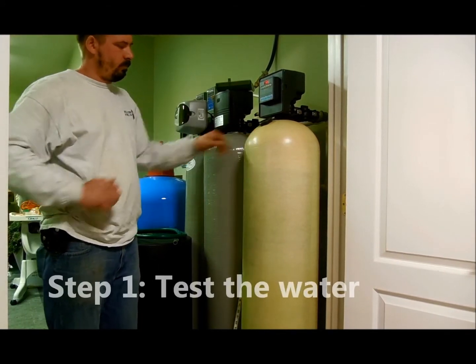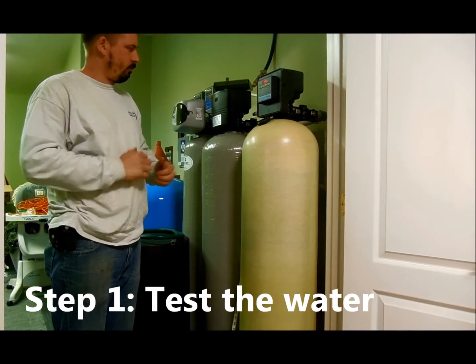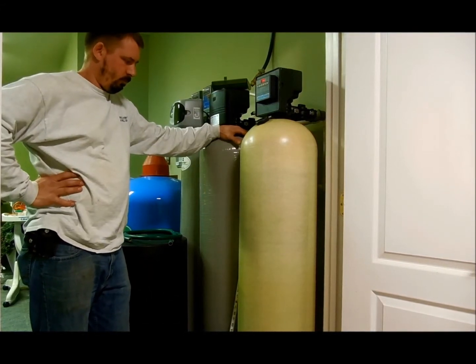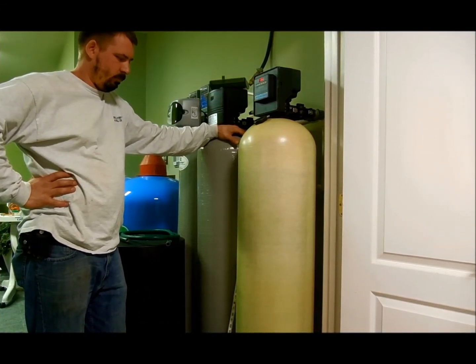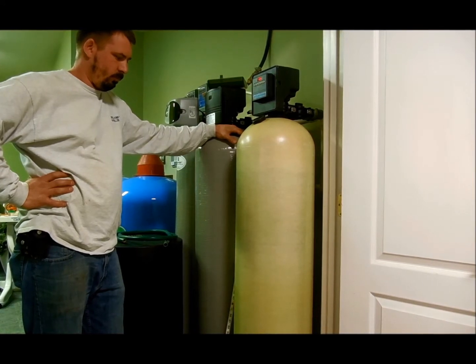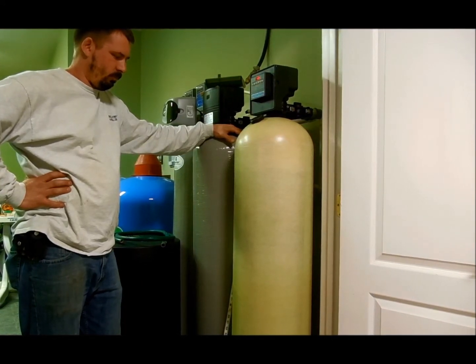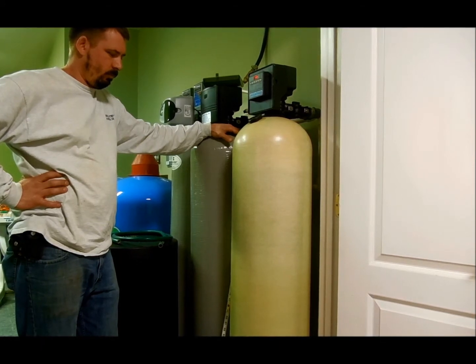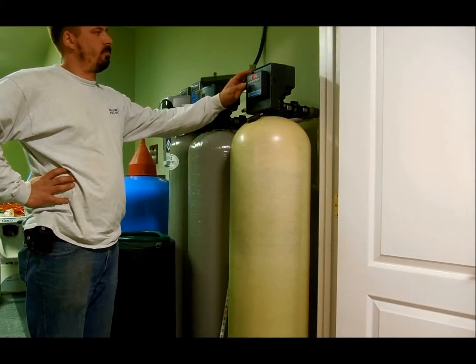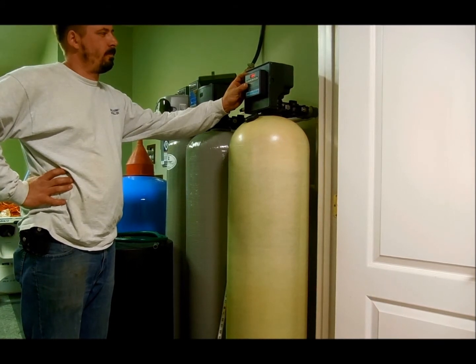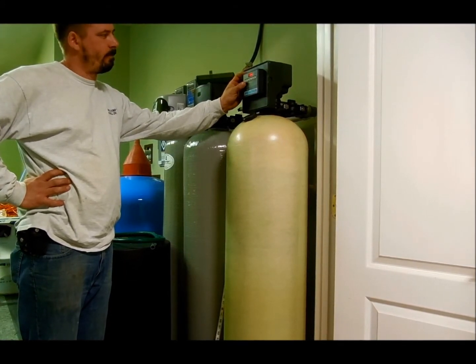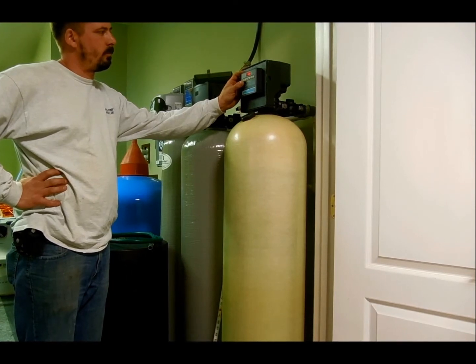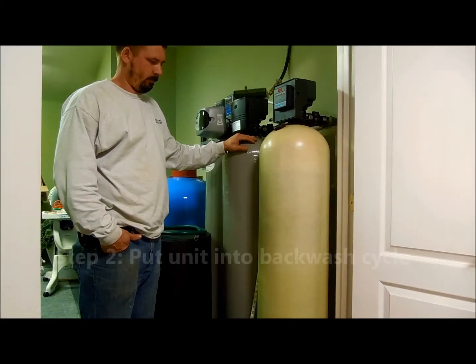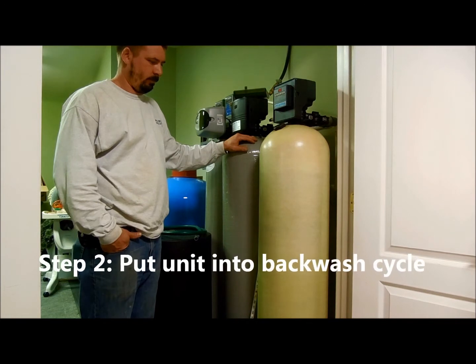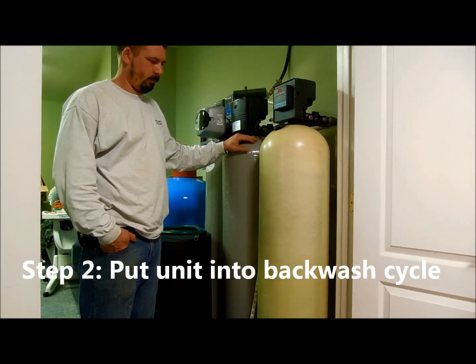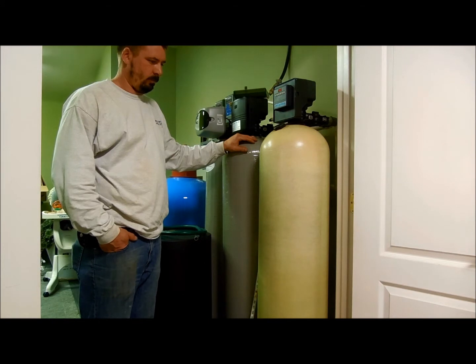The first thing we do is test the water to see what the pH is before we start the service. If it is 7 or above, that is fine, but if it's below 7, we will know to service it sooner the next time. We then start the backwash cycle on the automatic filter head. This is to eliminate any sediment on the top of the bed of calcite and just to see if the filter is functioning correctly. Every manufacturer has a different way to regenerate their filter, but if you start the backwash, you'll hear the water flowing and you'll know that it is in backwash.